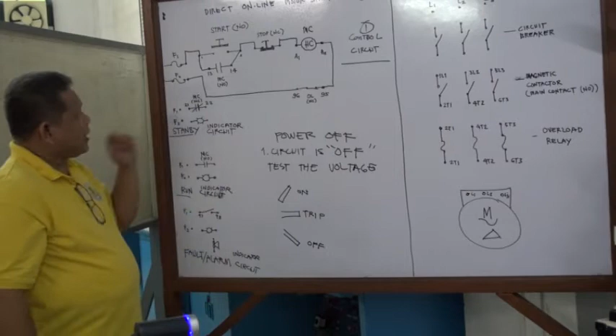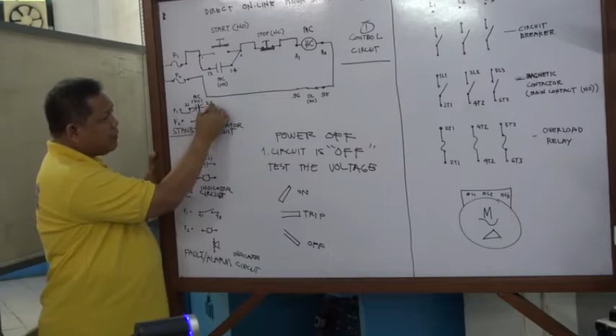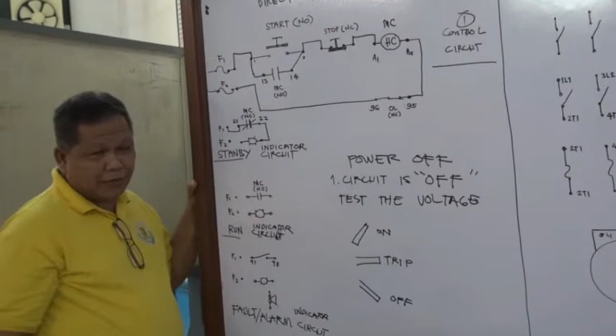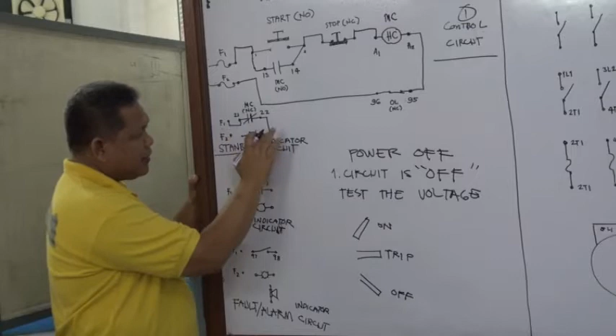Okay, so what we are going to do is this: Fuse 1 will be connected to terminal 22 of the magnetic contactor, which will be connected to our indicator lamp on one terminal, and the other terminal of the lamp to fuse 2. But let me go one by one so it's not confusing.